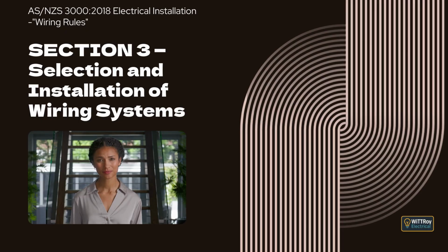This clause explains that earthing conductors do not need to be green and yellow in certain cases, such as bare or aerial earthing conductors, suitable screens used as earthing conductors, insulated earthing conductors not manufactured in green and yellow, or multi-core cables with a dedicated green earth, provided clear identification is applied where needed. Clause 3.8.3.3, Active and neutral conductors. This clause explains that active and neutral conductors may use alternative identification methods where conductors are within multi-core cables and clearly marked. Flexible cords are identified by approved alternative colors, or neutral conductors are distinguished by physical features such as ribs. Clause 3.8.3.4, Alternative and European cable identification colors.